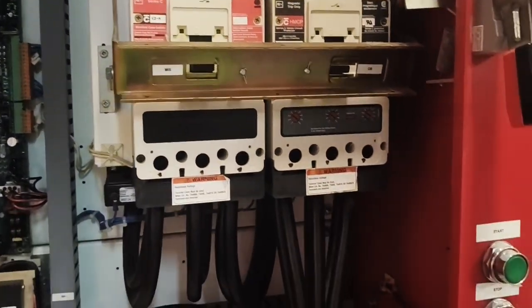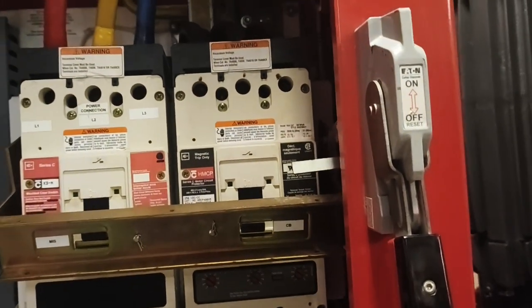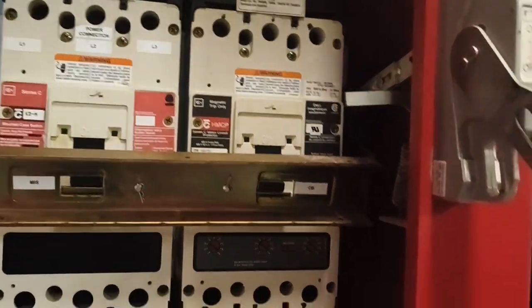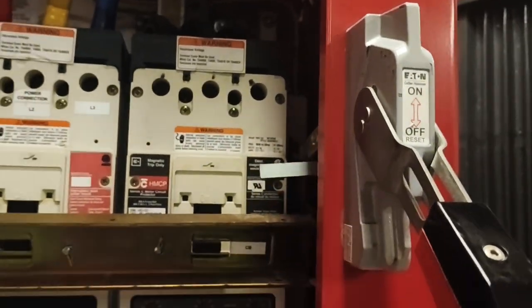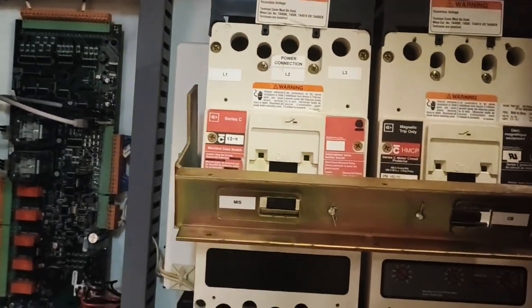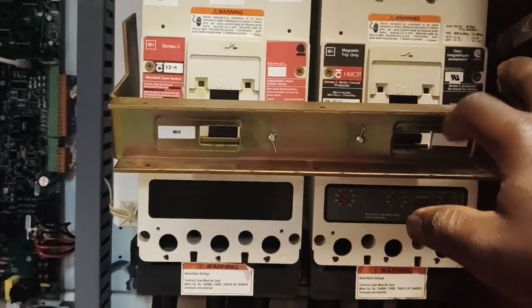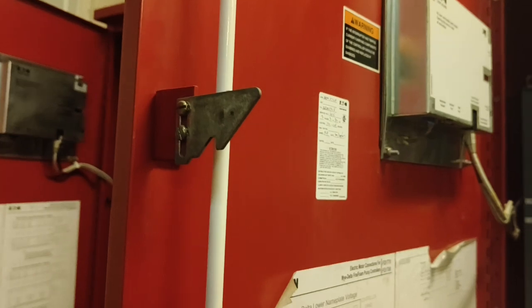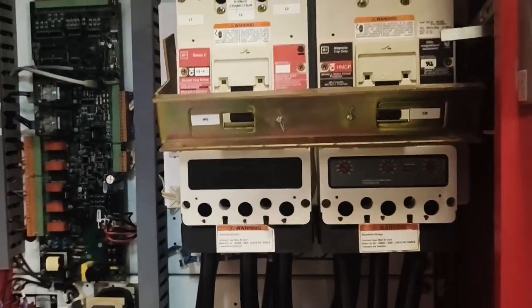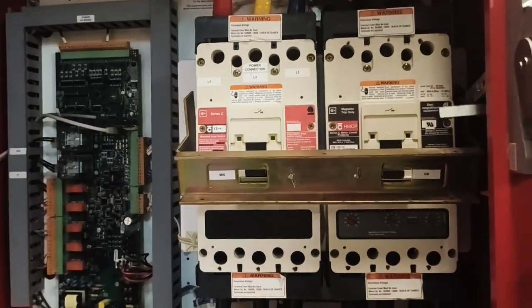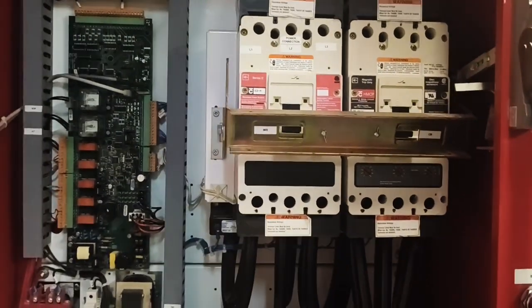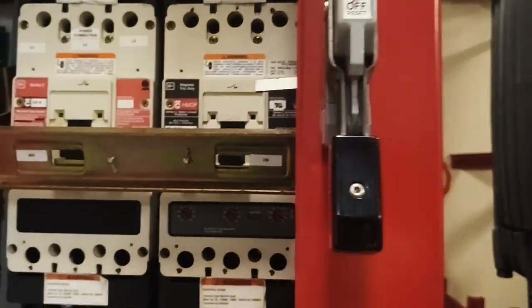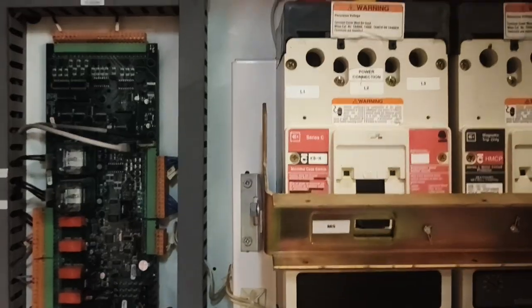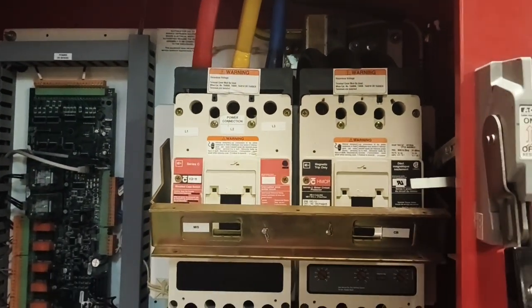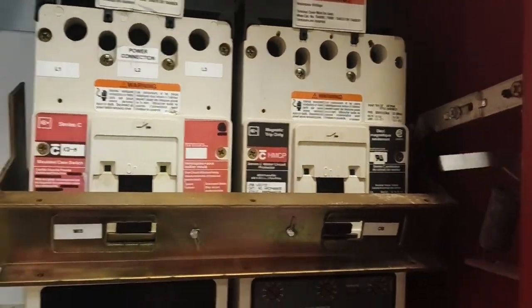Okay, so they work hand in hand, and this has been incorporated together, so that when you turn the switch it turns everything. But this here is a limit switch that holds it so that you cannot open it unless you turn it. You can see there is this bar here that does that work whenever it's closed. It's for safety purposes, so people cannot switch it on when it's in open condition. But as part of maintenance, when you want to switch on, probably to check the amps ratings, to check the amps actually produced versus the one showing on the control panel, that's how you can go about it. Just keep it down.